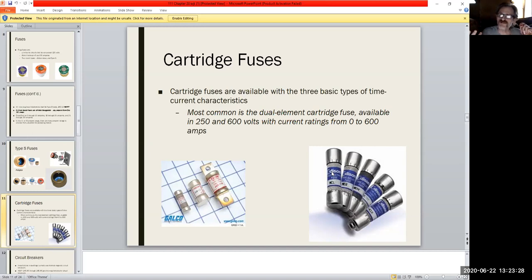They're all meant to blow over a given amount of current, and really what it comes down to is the time base involved. So don't just think that you can mix and match them, and if it's rated for 20 and the other one was rated for 20, that this is okay. You want to make sure it's the same exact style, because they do have different ones, and there will be a different time base involved, and that's really what you're looking at.